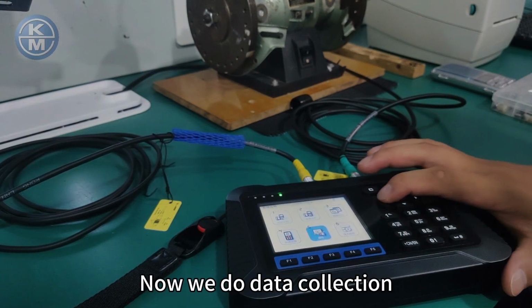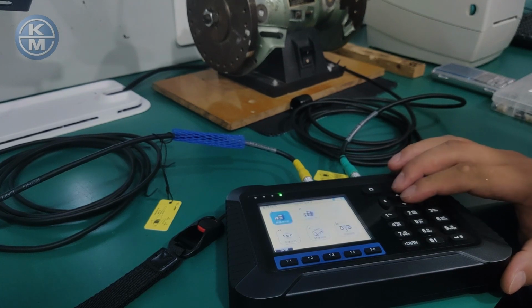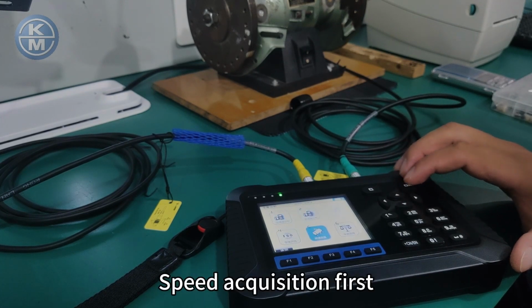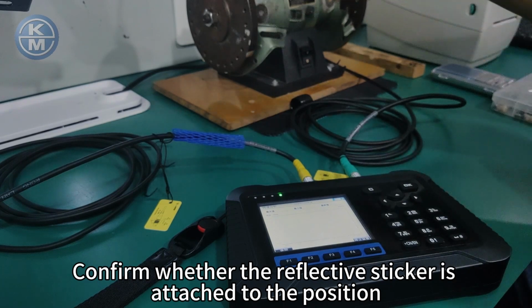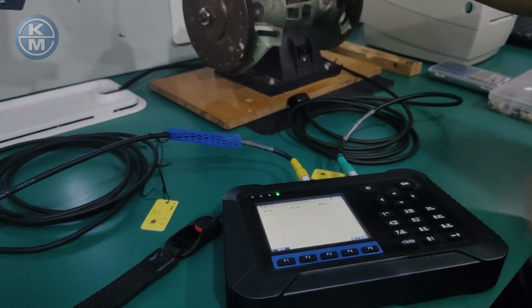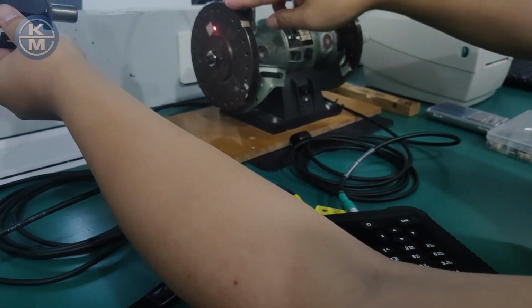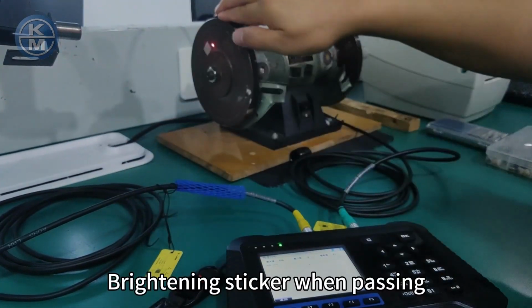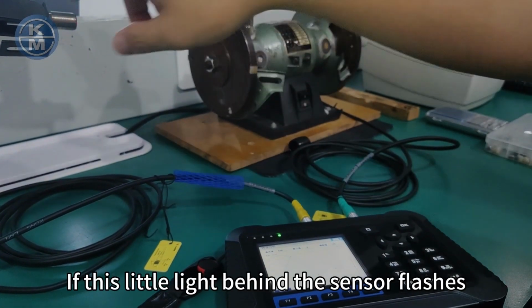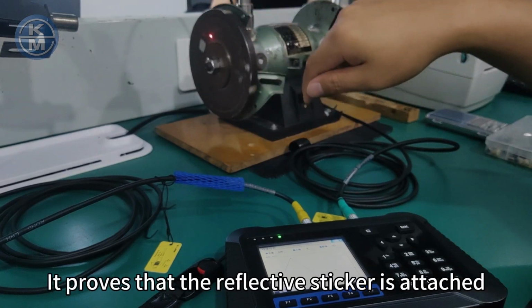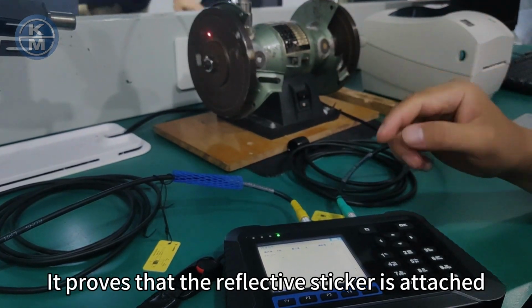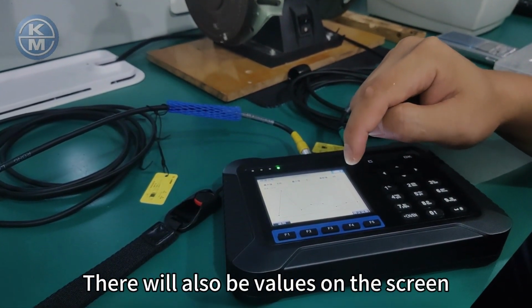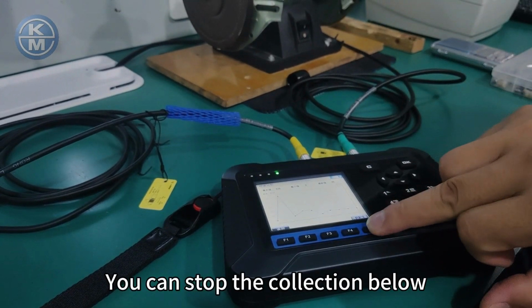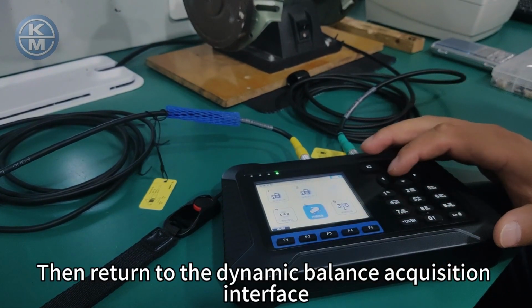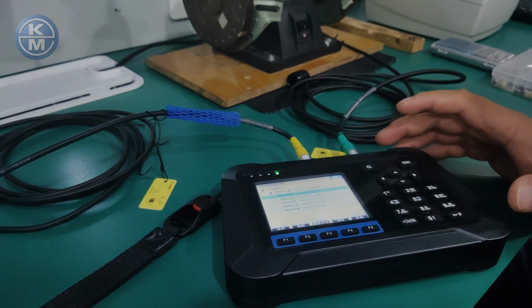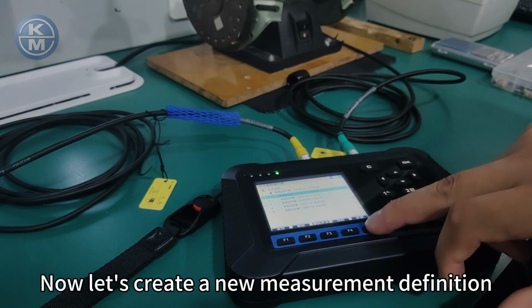Now we do data collection. Speed acquisition first. Confirm whether the reflective sticker is attached to the position. When the sticker passes, if this little light behind the sensor flashes, it proves that the reflective sticker is attached. There will also be values on the screen. You can stop the collection below, then return to the dynamic balance acquisition interface. Now let's create a new measurement definition.